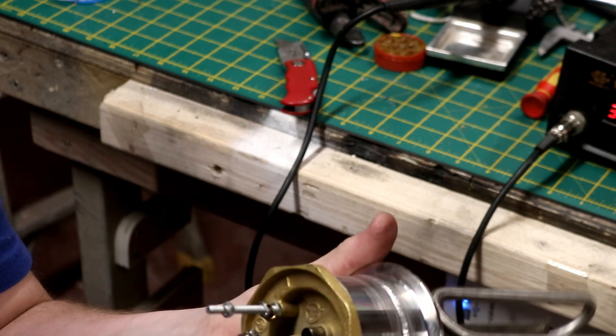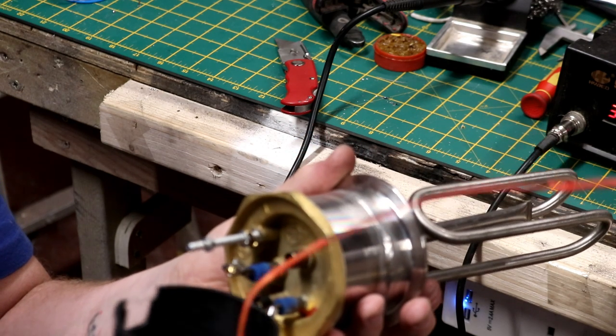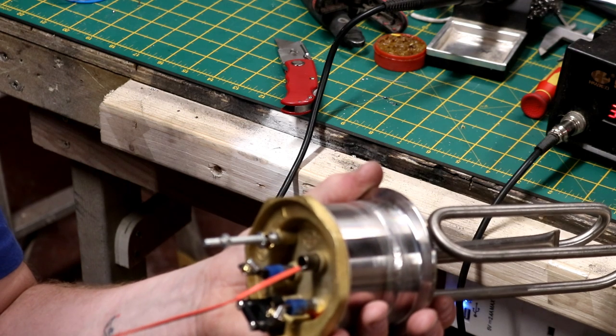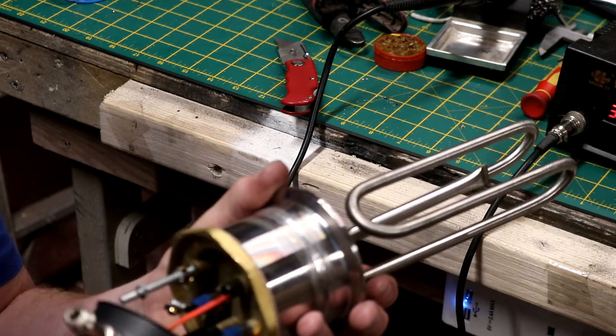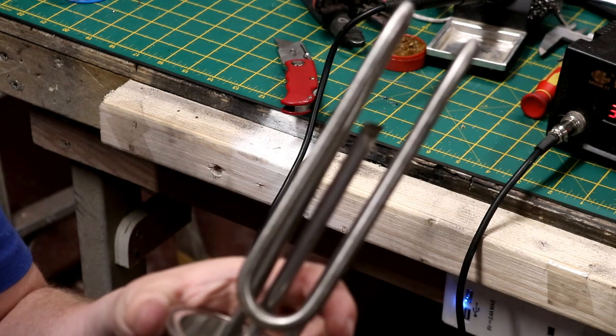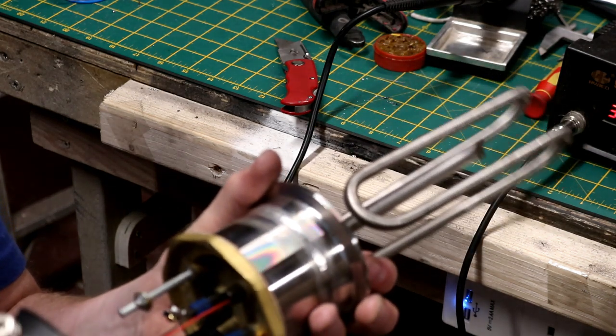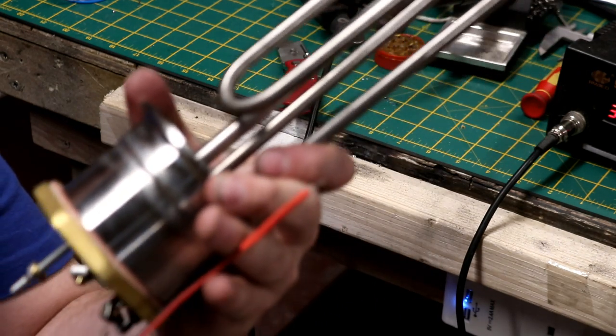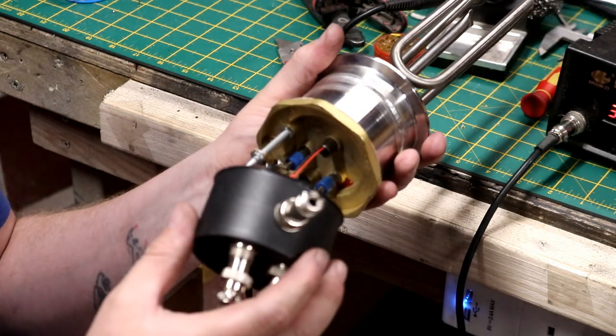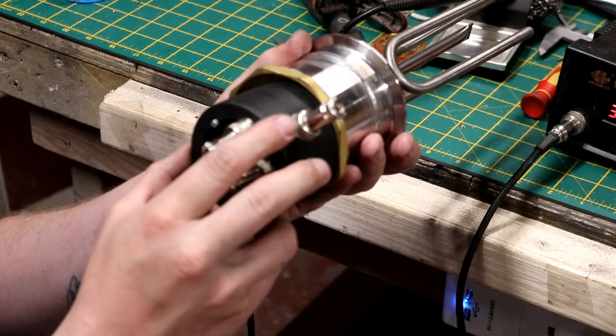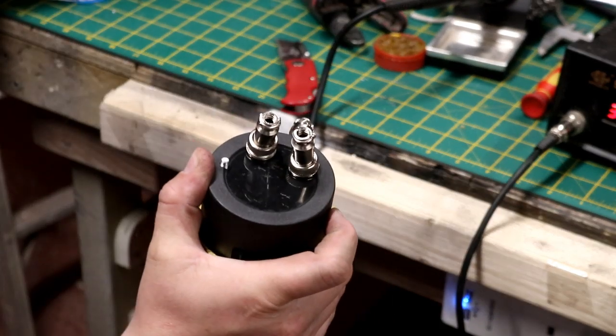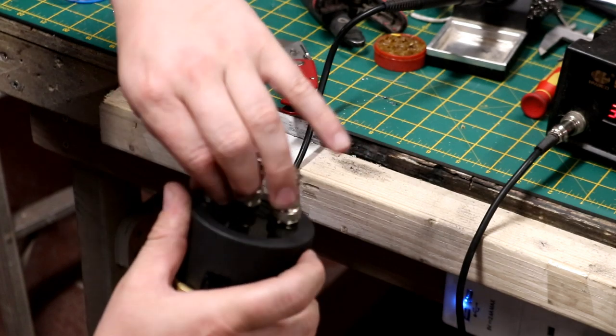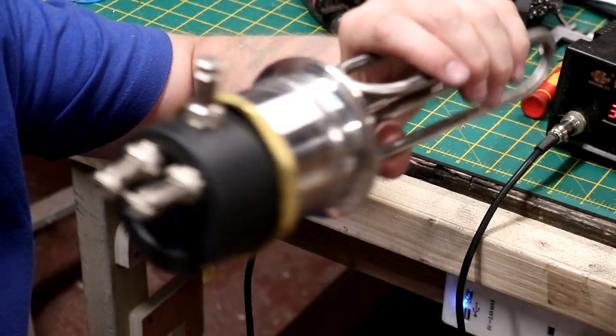So what we're going to do after we've wired this element up and the cable's going to come trailing out the base here and I'm going to leave the base open because then if any moisture gets in there it's got somewhere to drain. Sometimes it can be a false economy sealing it all up because if water does and it invariably will find its way in, it can't find its way out. So you can see we're going to utilise the probe that's already on the heating element, the thermal well should I say. And of course that PT100 is now... I've put some heat shrink on it to protect it from pulling apart. But it's now just going to slide straight down into that thermal well.